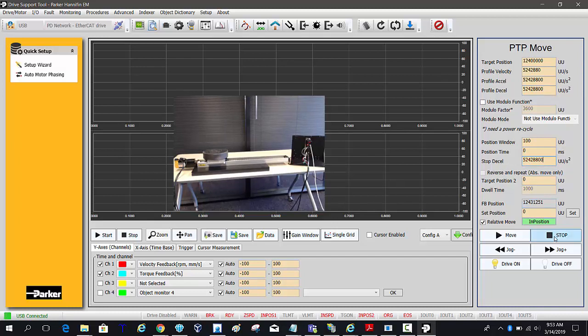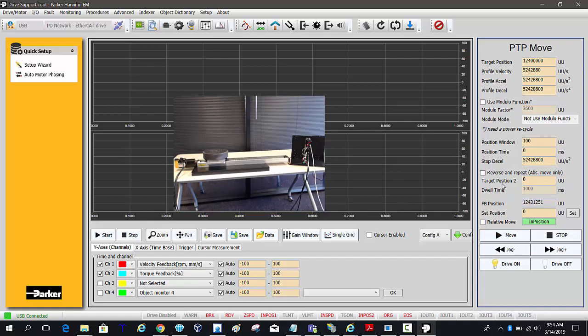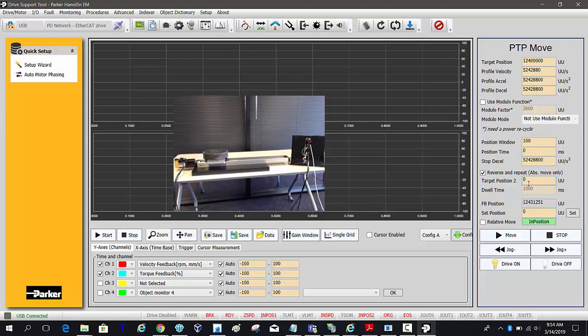The stop deceleration is used when you actually click the stop button. So if you're in the middle of a move and you click stop it will use this stop deceleration ramp. And then I don't want to do a relative move on a positioner like this. I want to move back and forth between those two absolute positions and move between 12,400,000 and zero.